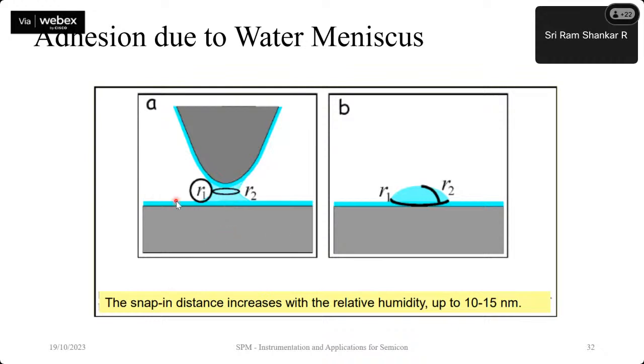In order to minimize the effect of this, it is possible that you can heat either the probe or the sample. Usually the sample can be heated, or you can purge a jet of nitrogen within this environment for some time, so that any water molecules and so on present on the sample can be carried away along with the nitrogen jet.